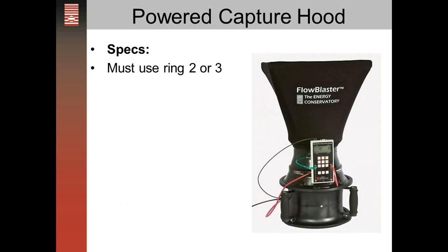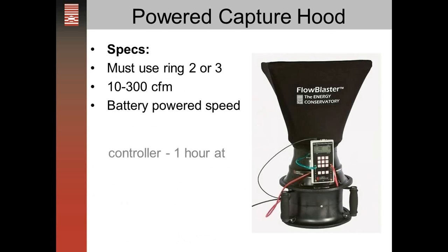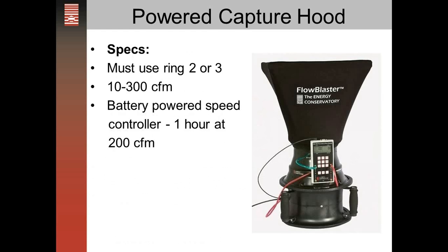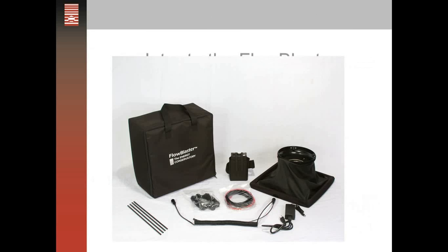You must use ring two or three, which gives you a flow range from about 10 CFM up to 300 CFM. It includes a battery-powered speed controller that gives you about an hour at 200 CFM, and longer than that at lower airflows. It weighs a total of about 12 pounds including the duct blaster fan. The inside dimensions of the hood are about 16 by 16 inches, and outside dimensions about 17 by 17.